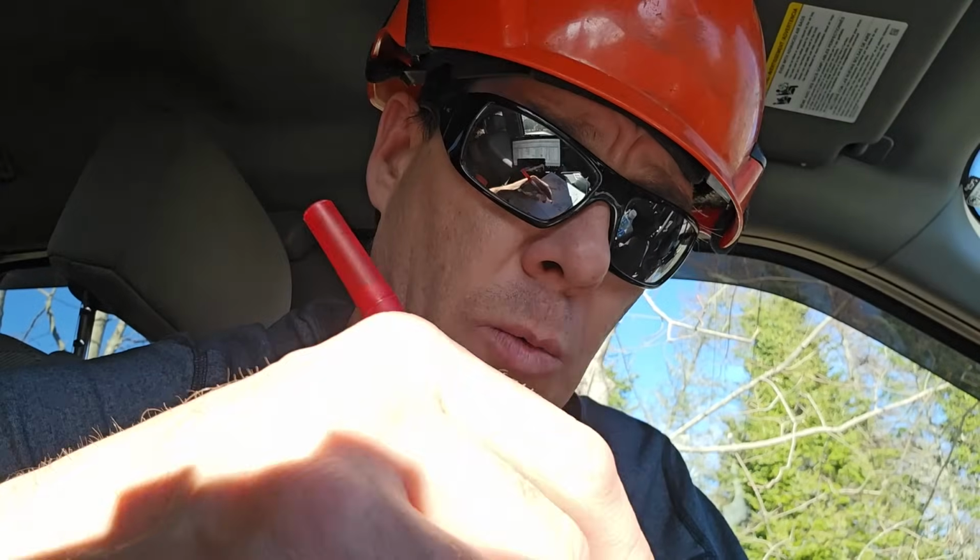All right, so we've got a radial permit in effect. This sideline's only one span. Pretty easy to figure out protection points on this one. So when they say a radial permit, there's no alternate feed coming into the work area. So that's why they just say to the end of the line. There's no other line feeding in.